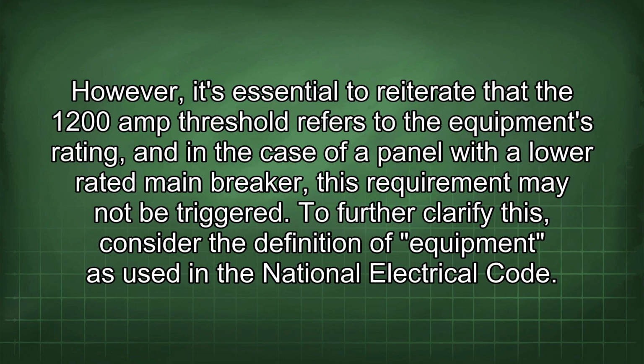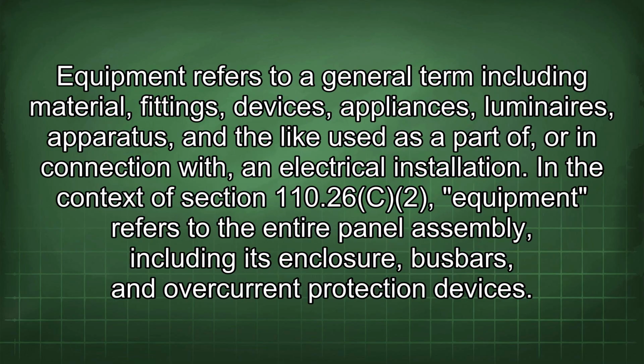However, it's essential to reiterate that the 1200 amp threshold refers to the equipment's rating, and in the case of a panel with a lower rated main breaker, this requirement may not be triggered. To further clarify this, consider the definition of equipment as used in the National Electrical Code. Equipment refers to a general term including material, fittings, devices, appliances, luminaires, apparatus, and the like used as a part of, or in connection with, an electrical installation.